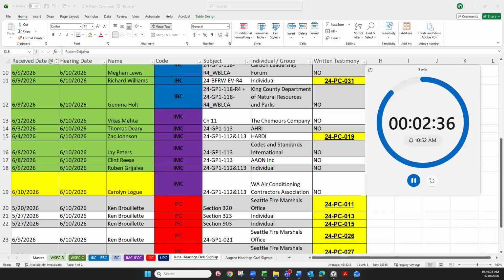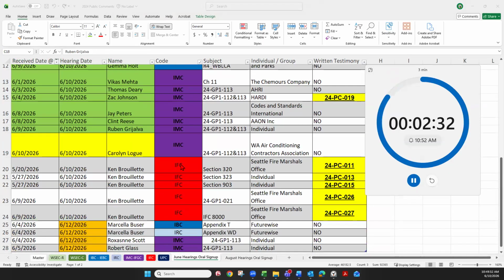I oppose the proposed alternative approval pathway contained in Proposal 24 GP1, 113, and 112 because it risks confusing energy efficiency qualification with product safety certification. Washington can and should support efficient low GWP heating and cooling equipment, but equipment using flammable refrigerants must be evaluated through recognized safety standards and certified by qualified independent testing laboratories. The current U.S. safety framework exists for a reason. Standards such as UL 2-40 and UL 2-89, ASHRAE 15, the Mechanical Code, and the Fire Code address refrigerant charge limits, leak scenarios, ignition risk, ventilation, labeling, installation, servicing, and emergency response considerations. Those are safety questions, not just efficiency questions.